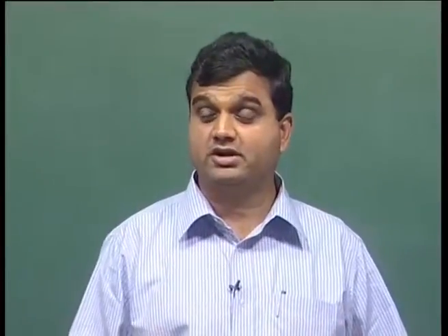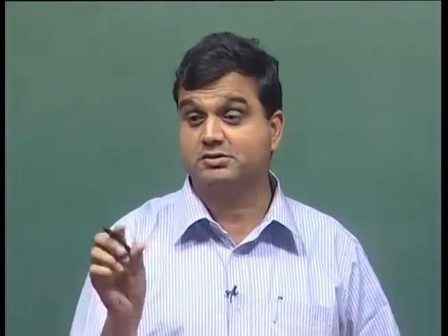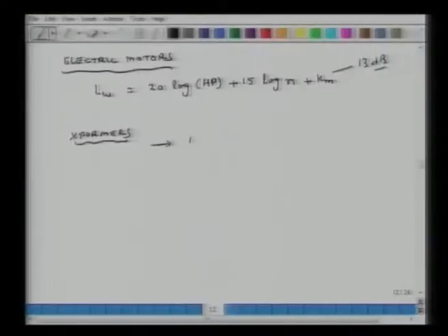By eddy currents. The electromagnetic forces are pulsating based on your AC frequency, and they induce vibrations in the metallic structure. If it is a 50 hertz current supply, as in India, then it is typically twice that number, a 100 hertz signal, or 120 hertz in countries like the USA. So a lot of times some of these signatures you can attribute to a transformer. Sometimes you have a PCB which has an inductor on it, nothing is moving and you hear that noise. Most likely it is coming from some inductor. This relates to AC frequency.